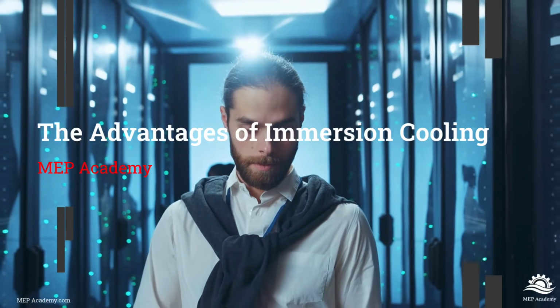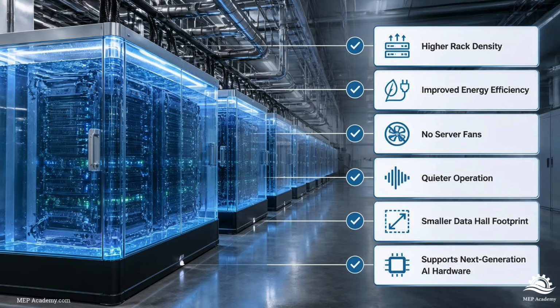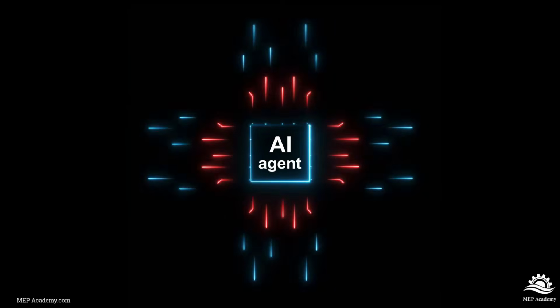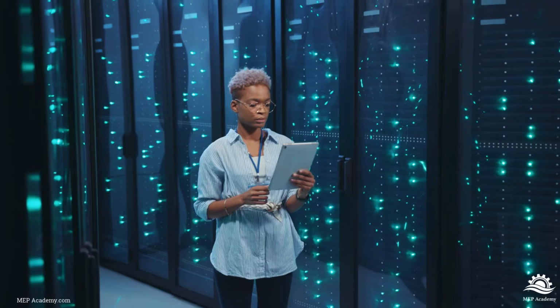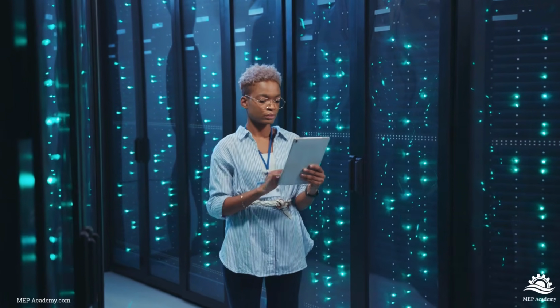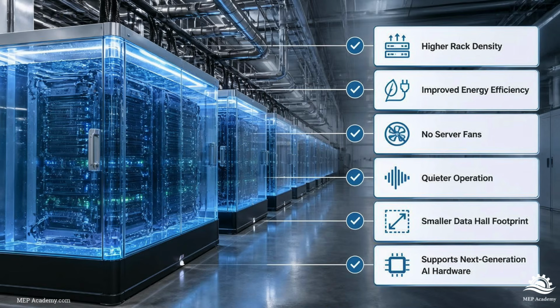So why are companies investing billions into this technology? There are several reasons. First, significantly higher rack densities. Second, improved energy efficiency. Third, reduced fan energy consumption. Fourth, quieter operation. Fifth, potentially smaller data halls. And sixth, the ability to support next-generation AI hardware. Perhaps one of the biggest advantages is consistency. Every electronic component experiences nearly identical cooling conditions. There's less concern about hot spots forming inside the server.